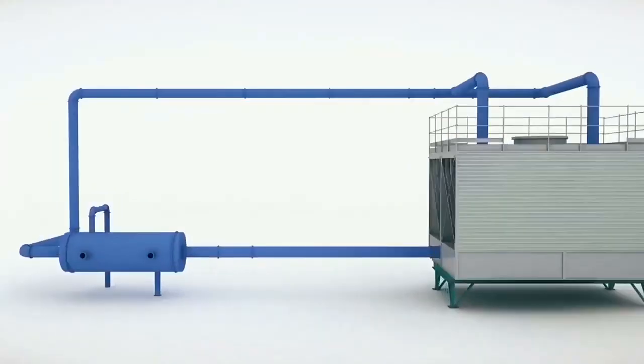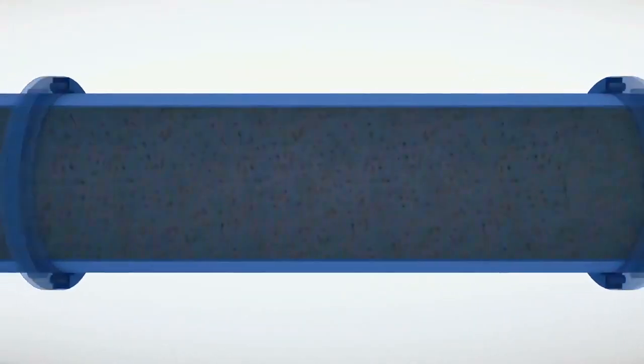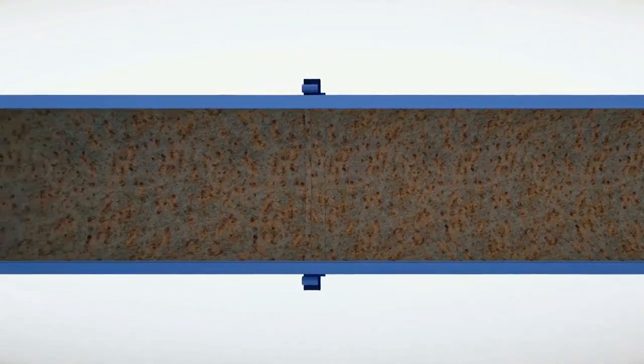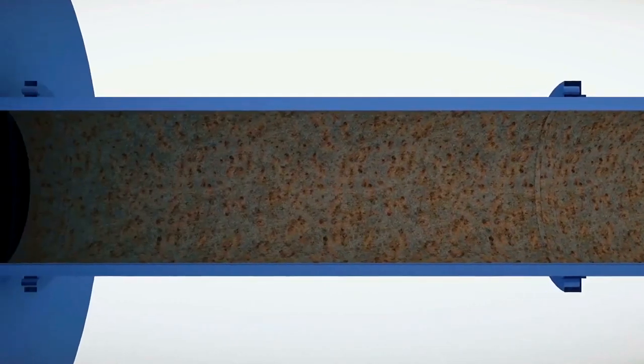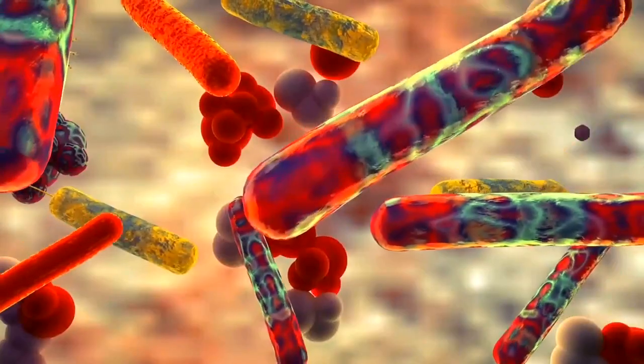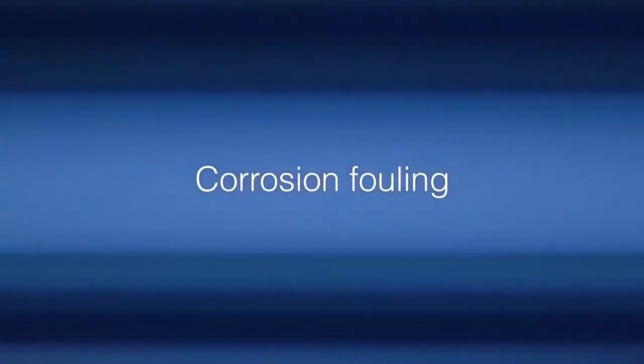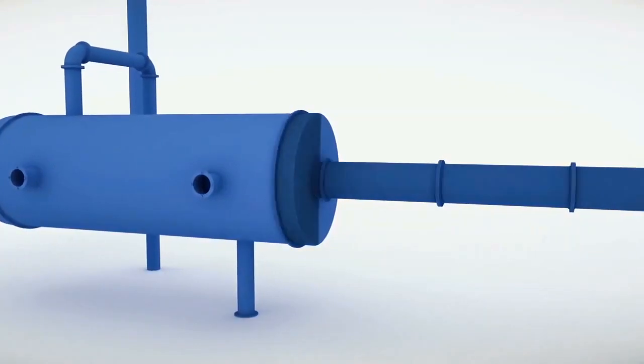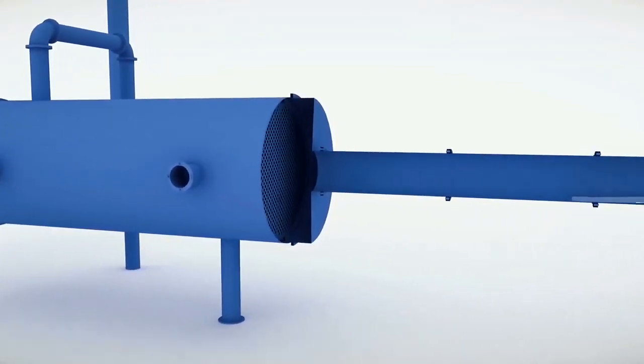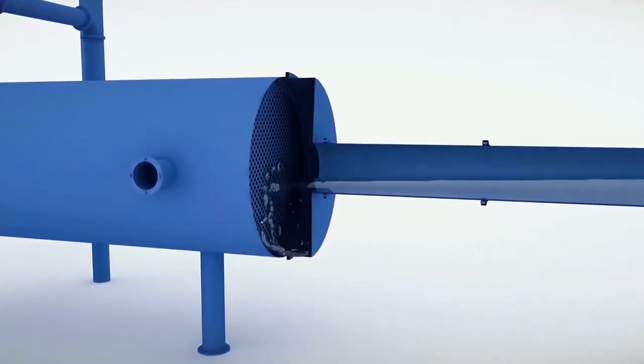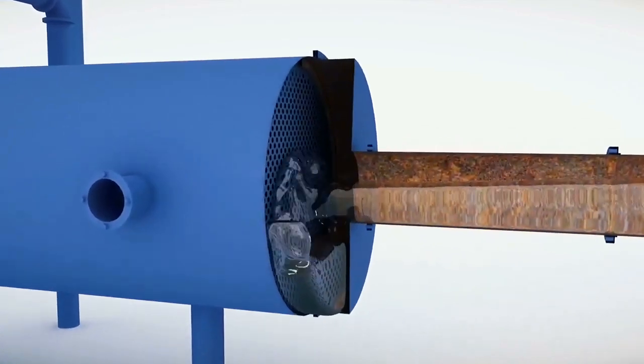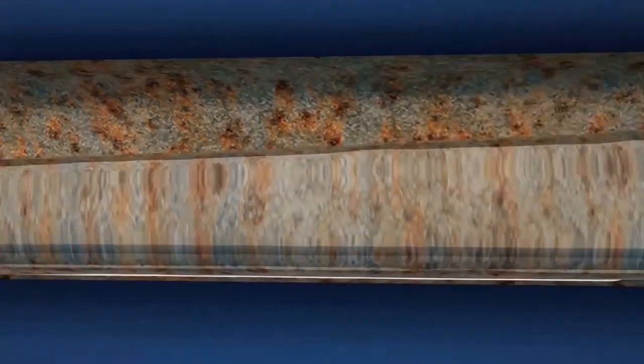Biofilm fouling. 4 times more insulating than scaling, the warm water conditions and the dirt layers create the perfect breeding ground for bacteria and algae that results in a film inside the tubes and can spread harmful bacteria to cooling towers as well. Corrosion fouling. Deterioration of metallic parts due to various reasons results in formation of iron oxide layers over the tubes, while the bacteria from biofouling feed off of it, causing holes and pits inside the tubing.